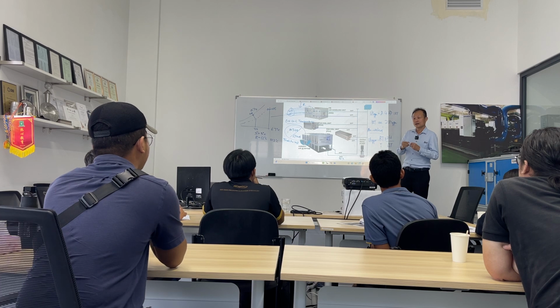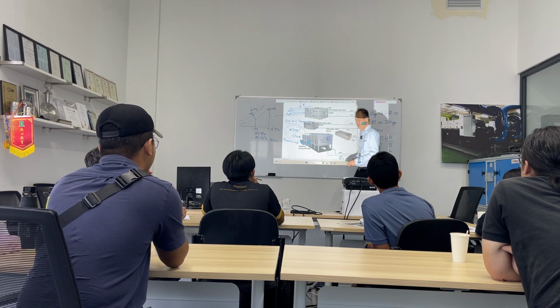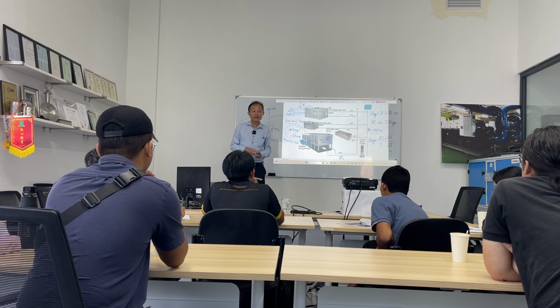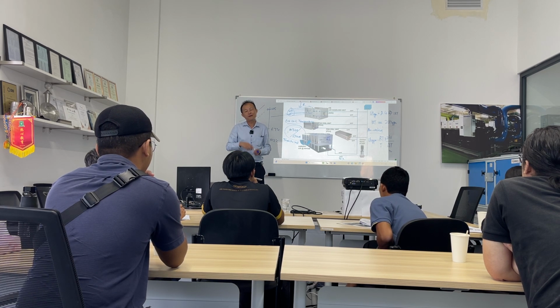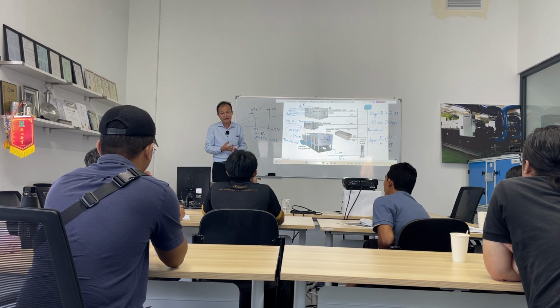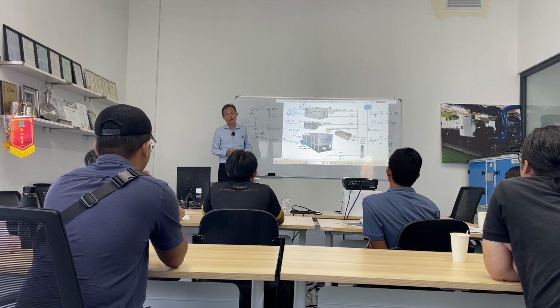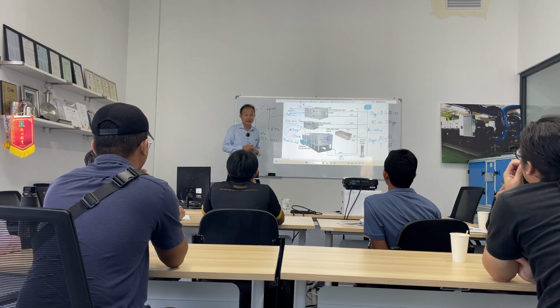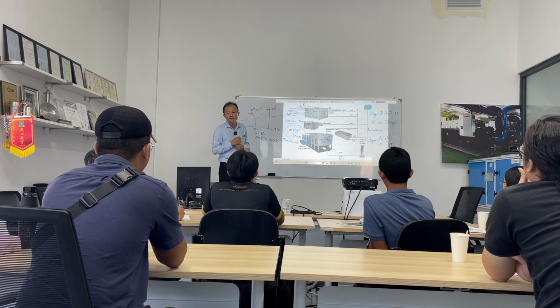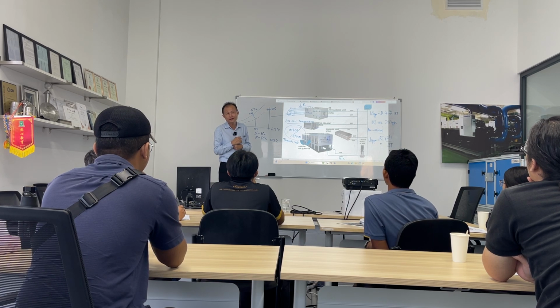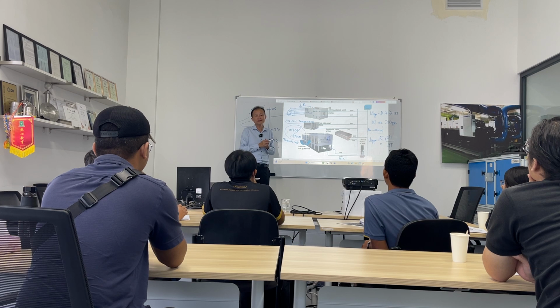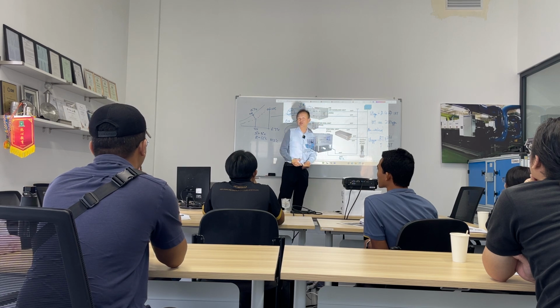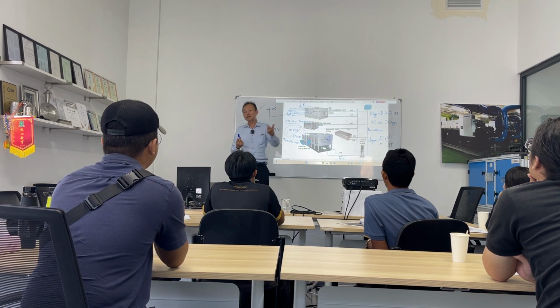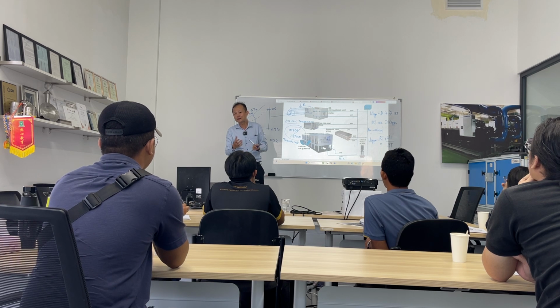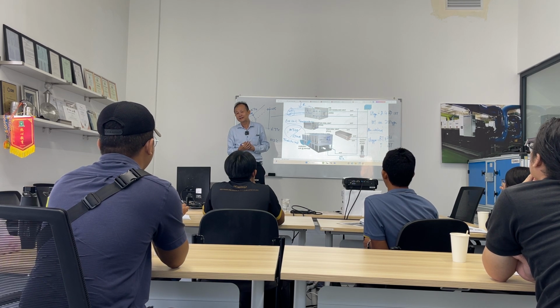So if I reduce the flow rate, what component do you think benefits first? In terms of sizing, if you are the designer, the pump size will reduce, right? Another component that can possibly reduce is the piping size, valves. Maybe your pump motor also reduces, cable reduces, starter reduces, control panel reduces. You see the impact, right?